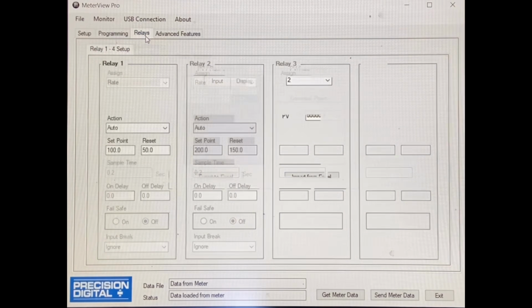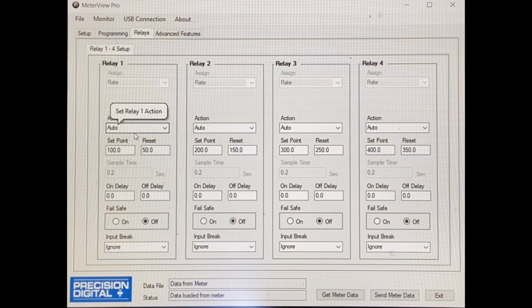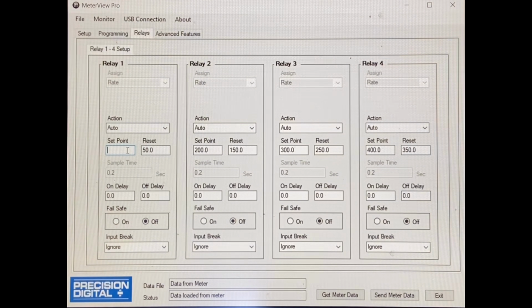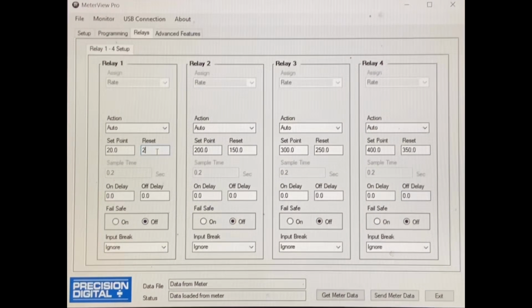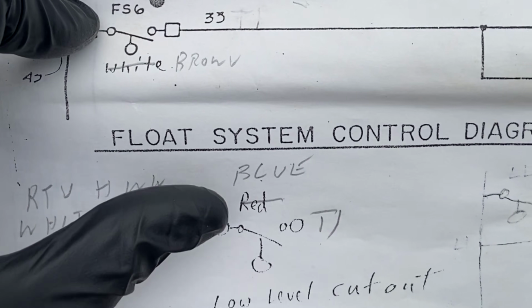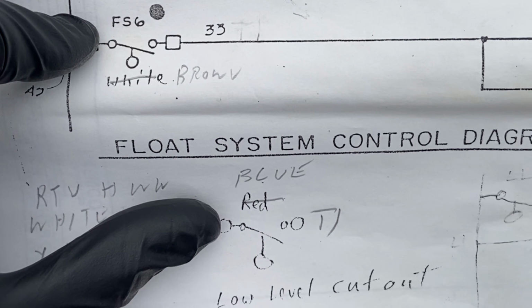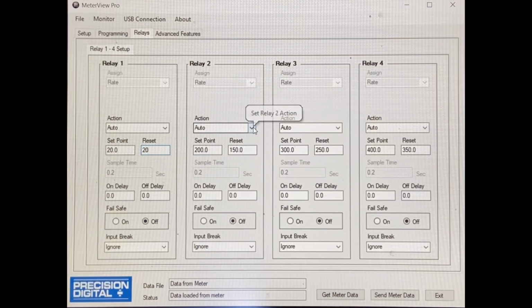Then we can go up and start configuring our relays. So our relay 1 is our low level, which was a single float. So the action is going to be auto, which just means it goes on and off as the level reaches whatever you set it to. So the set and reset will be the same in that row because there is no pumping range with a single float.